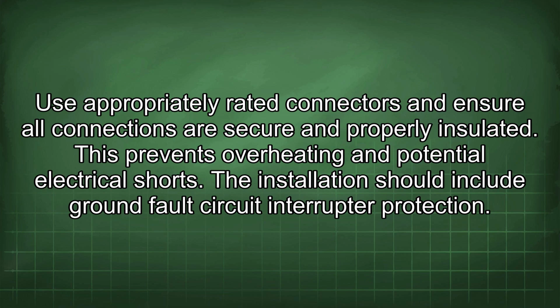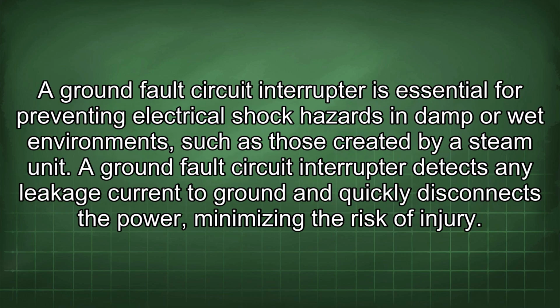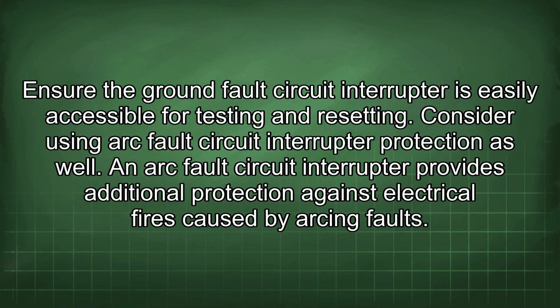The installation should include ground fault circuit interrupter protection. A ground fault circuit interrupter is essential for preventing electrical shock hazards in damp or wet environments, such as those created by a steam unit. A ground fault circuit interrupter detects any leakage current to ground and quickly disconnects the power, minimizing the risk of injury. Ensure the ground fault circuit interrupter is easily accessible for testing and resetting.